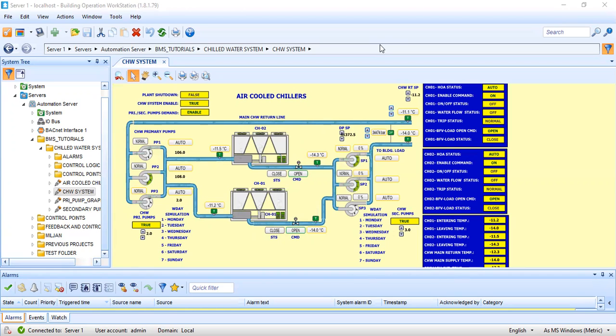A method of statement is a narrative you prepare — for example, for an air handling unit, this will be the method of statement for doing testing and commissioning. You do a step-by-step procedure. You start with your graphics: create a screenshot of the graphics and explain in the method of statement how you intend to give the testing information. You will start with your BMS graphics showing all the control and monitoring points, which should be part of the BMS data points schedule.